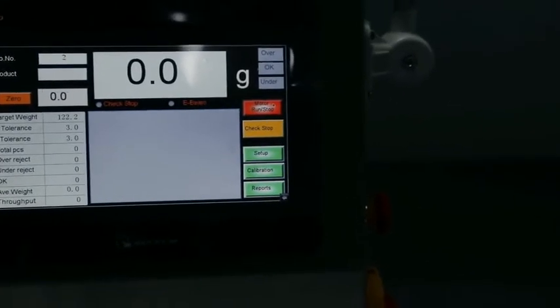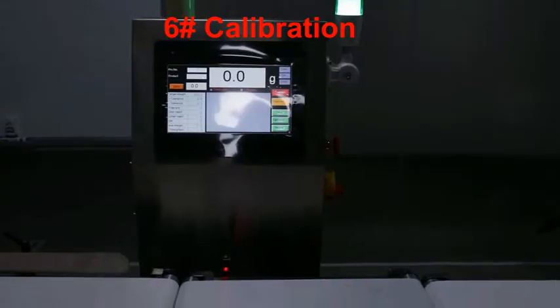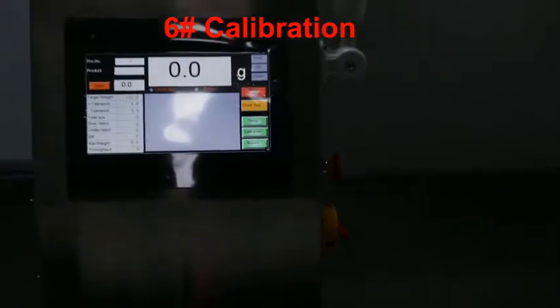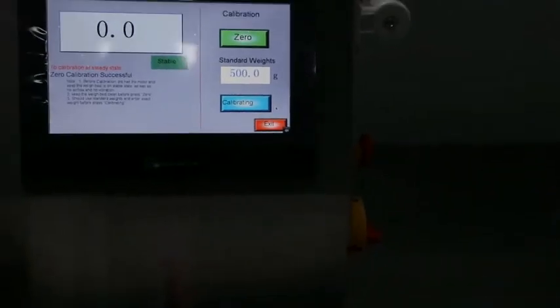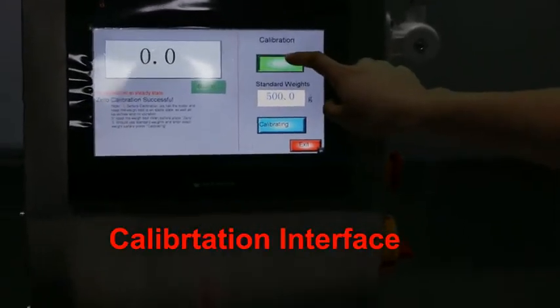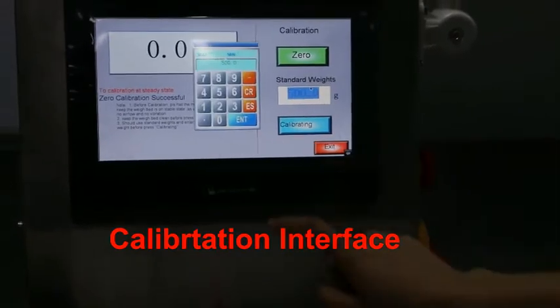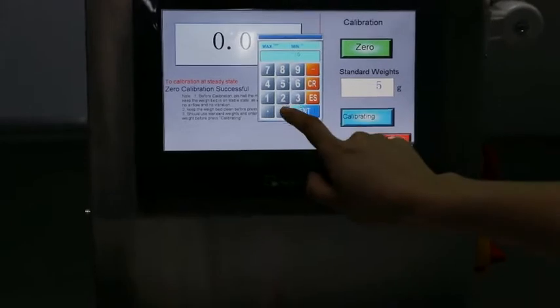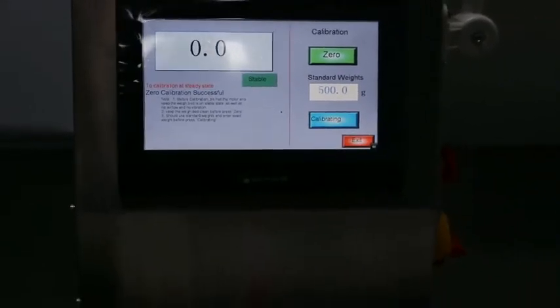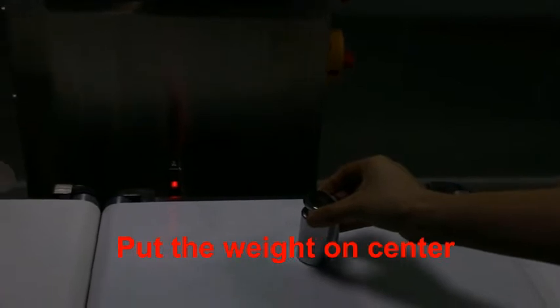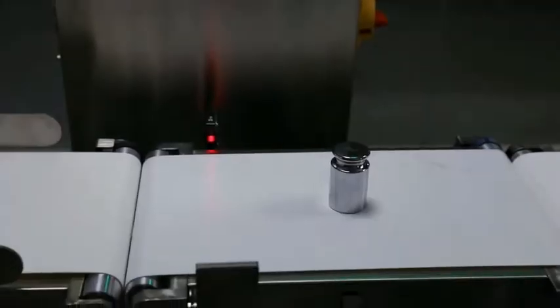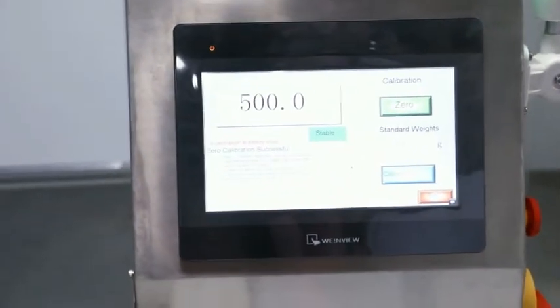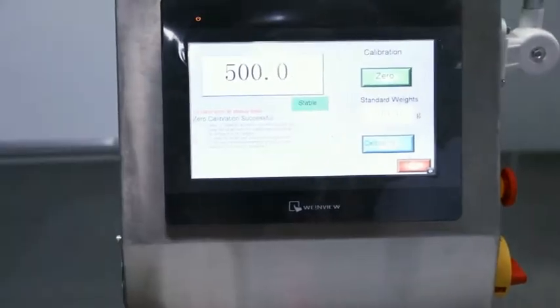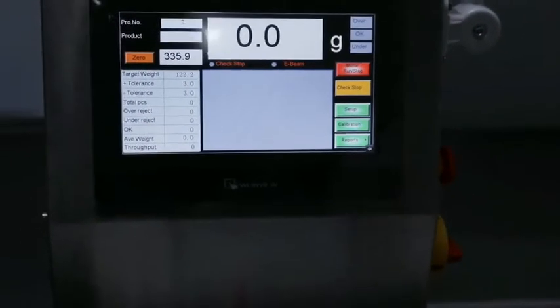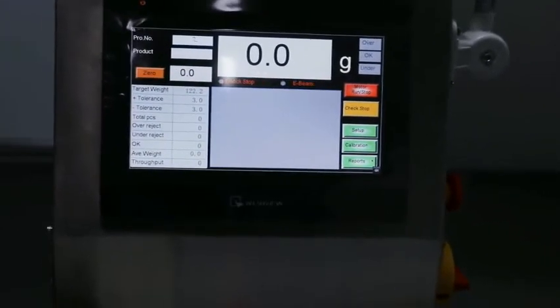And then the next section is about setting up the parameter. Now we need to set up the calibration. Click on the calibration, you go into this interface. Click the zero button and insert 500 gram, enter. And then put the weight here gently on the center of the weighing section. And you get 500 gram here. Zero calibration successfully done. Then it's okay. Exit. Move the weight. Then you have done your calibration part.